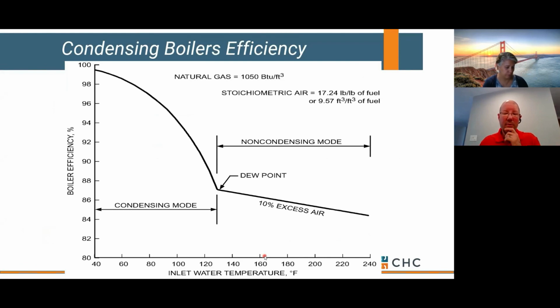If you're a condensing product, it means your materials can handle low return temperatures. And low return temperatures means we're taking some moisture out of the products of combustion. That's very acidic, so typically you're dealing with stainless steel construction in order to deal with that. So with a condensing boiler or water heater, you're looking for the coldest temperatures you can get to maximize your efficiency. Basically you're sending less heat up your flue or your stack, which makes your boiler or water heater more efficient.